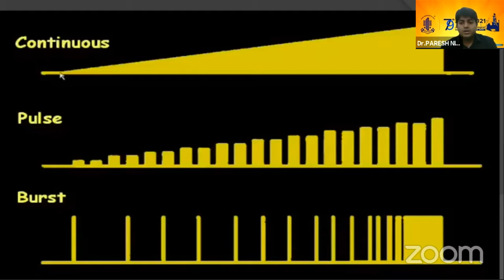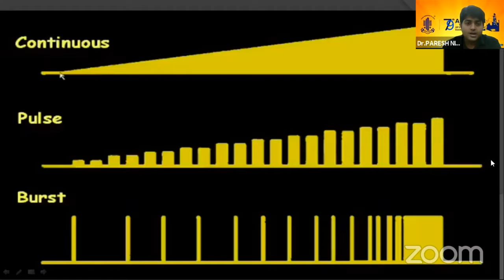Now coming to the phaco power modulation, basically there are three phaco power modulation being used. One is the continuous, in which the power increases as we go forward in the stage 3, foot pedal stage 3. In pulse mode, the interval between on and off is decided, and the energy increases as we go forward in step 3. In burst mode, the energy dissipated is kept constant, but as we go forward in this foot position 3, the interval between on and off cycle decreases, and at the end of the foot position 3, it basically turns into a continuous phaco mode.